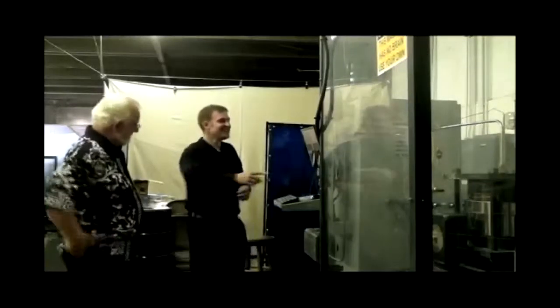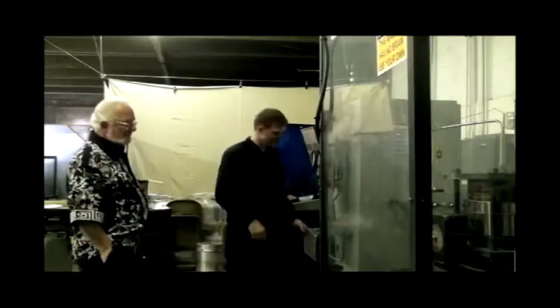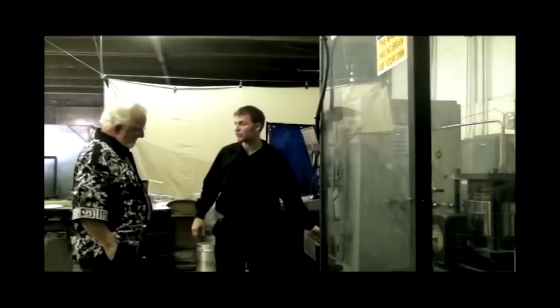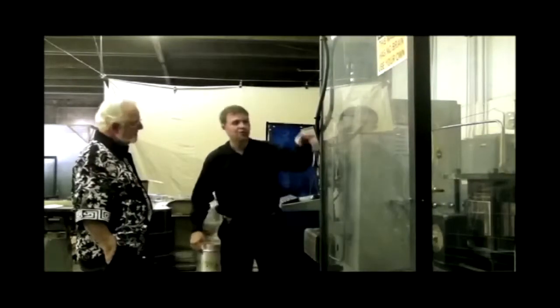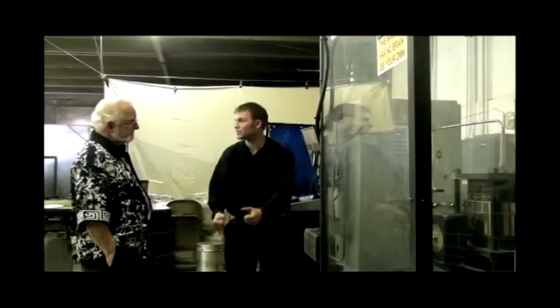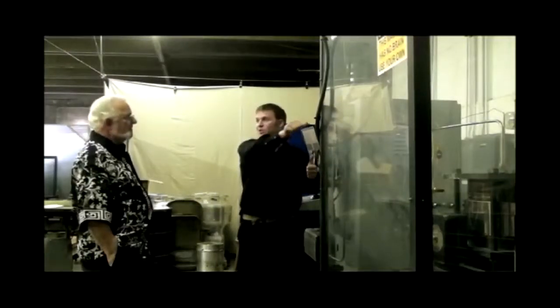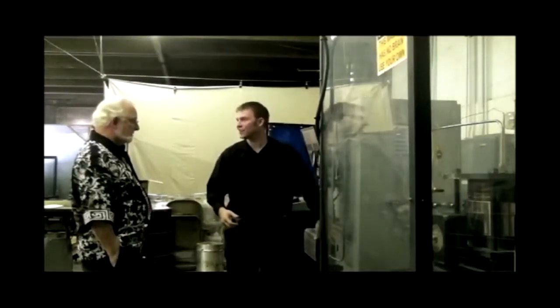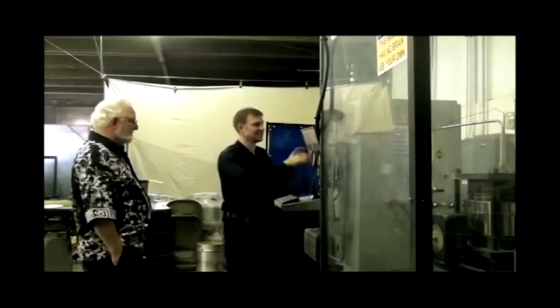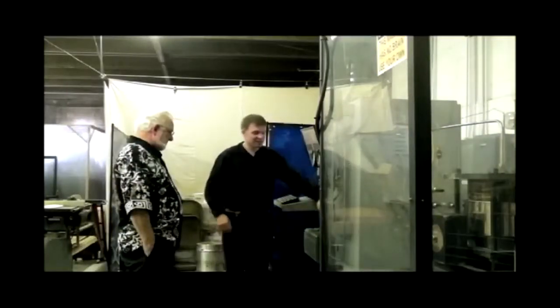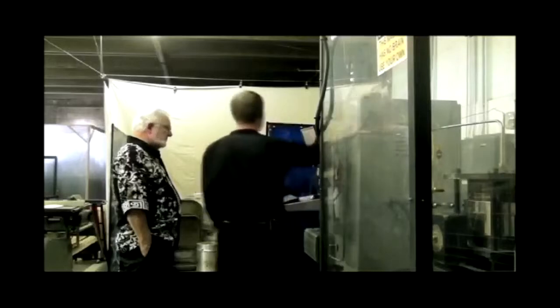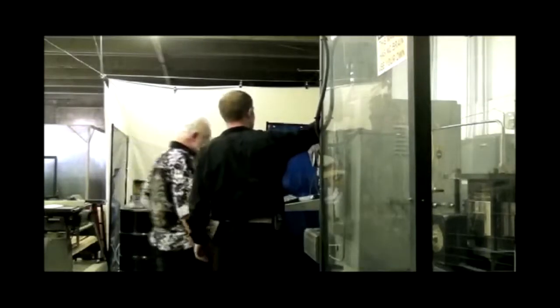So what I did as a solution was realize I can measure a gas at that pressure. By running this tube all the way through, as the water expands it pushes back on the air trapped inside here, and pushes it to read my meter. This panel is separated from the unit itself, which is why it's mounted with these little gray paint blocks. So that's what these meters are reading—they're reading the pressure of it.